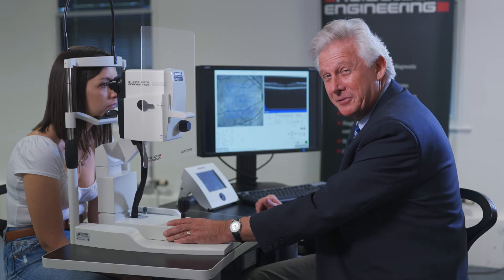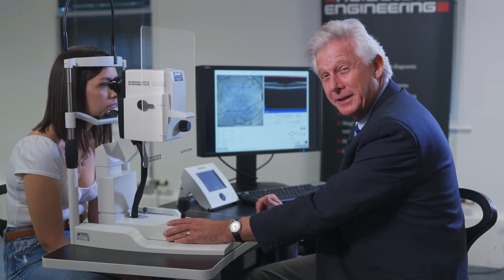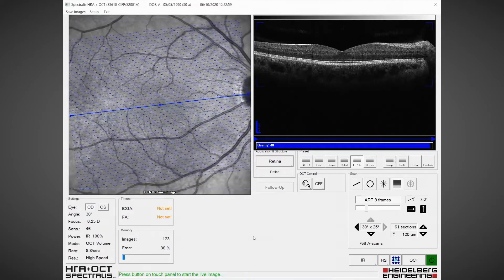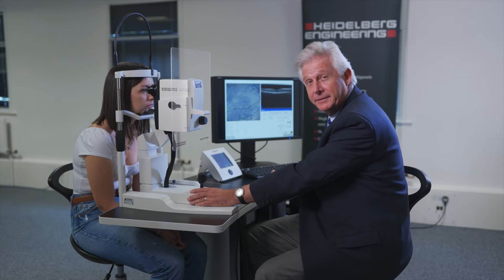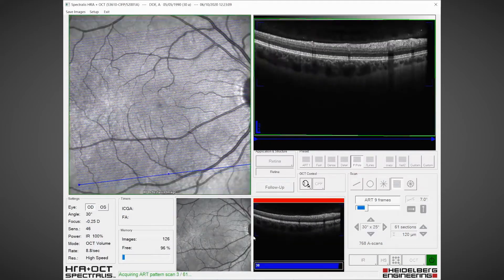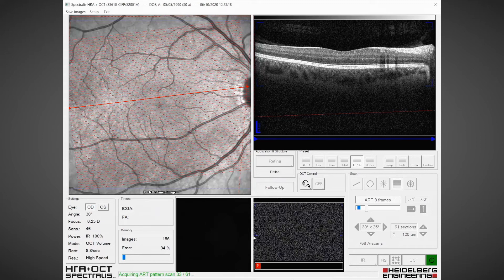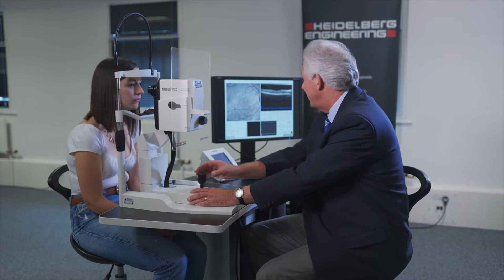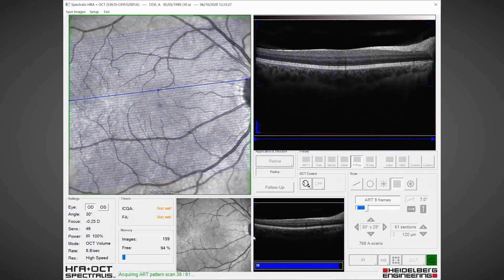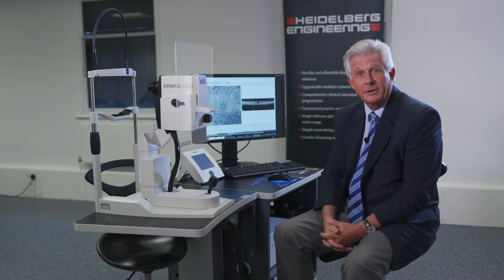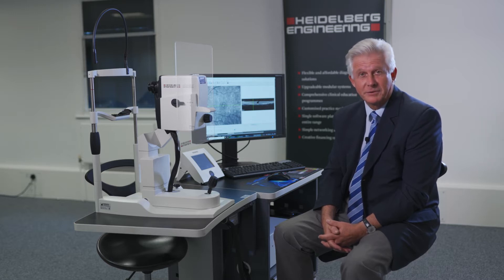The patient has no time to move away from the scan. Let me show you slowed down what is really happening with our live eye tracking. Selecting a posterior pole scan, we're doing an averaging of nine frames per B-scan, which is possible because of TrueTrack live eye tracking. When the patient moves away, the scan stops because the instrument no longer recognises the retina. When the patient comes back in position, we catch up exactly where we left off and continue to track the eye live — even if they move.